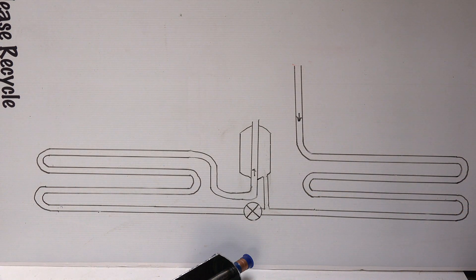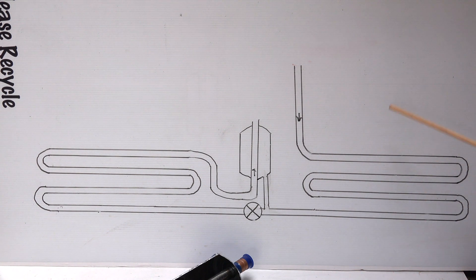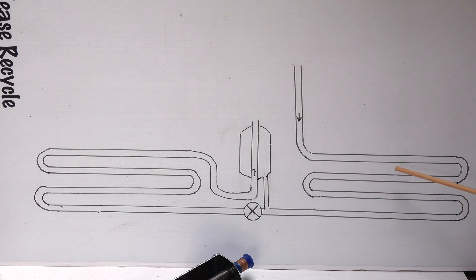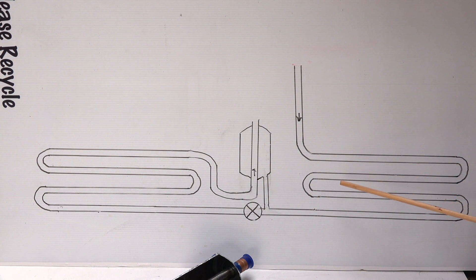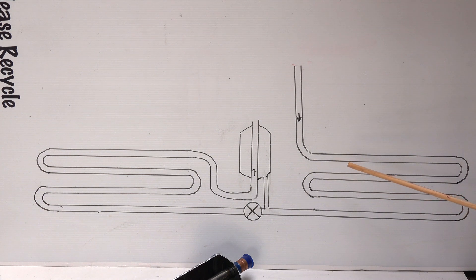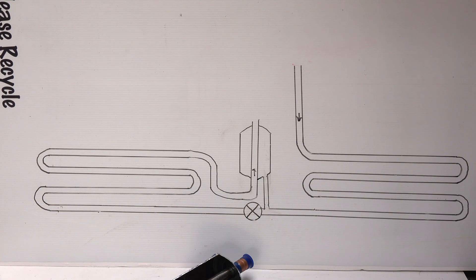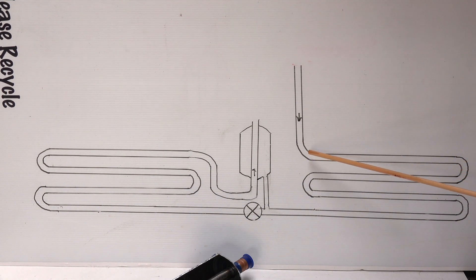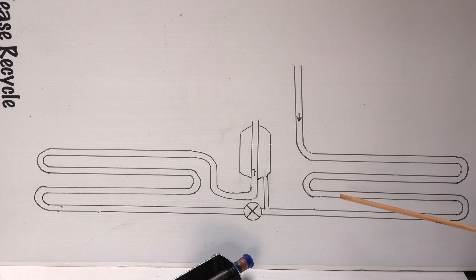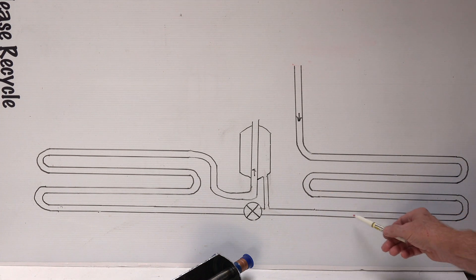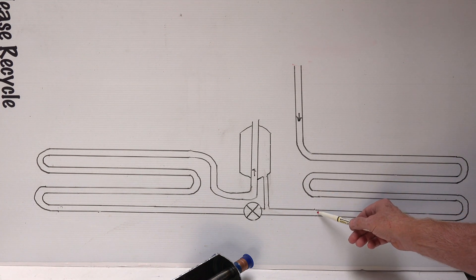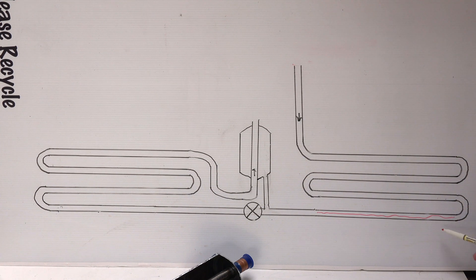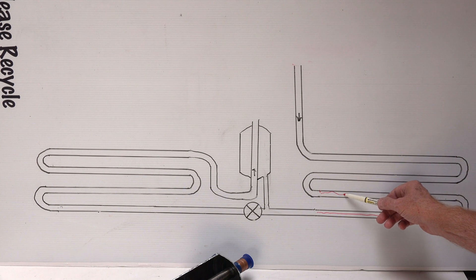Then sometimes you would get these mismatches and they wouldn't balance out well and the head pressure, even though you got plenty of air moving across the coil. Now this is the indoor coil in heat. There's plenty of air moving across it. The liquid line temperature has a lot of subcool, probably more than it should have, and you still have high head.